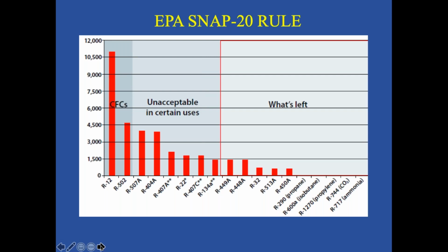So which refrigerants will now be unacceptable? R12 has already gone, 502, 507, 404A, 407A, R22, 407C, and 134A - all these refrigerants will be phased out. What will be left is 449A, 448A, R32, and lastly, the last four refrigerants: hydrocarbons - propane, isobutane, propylene - carbon dioxide, and ammonia.